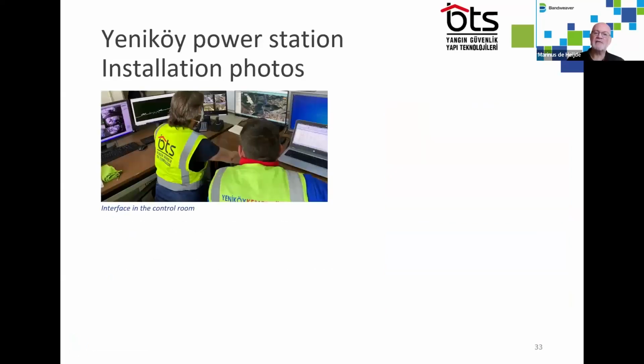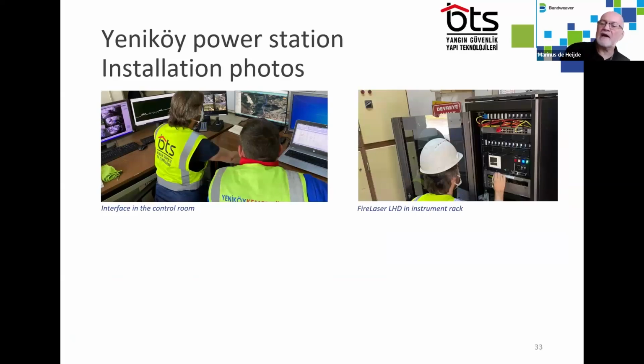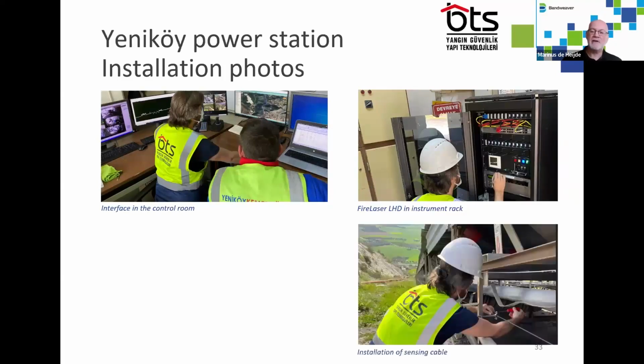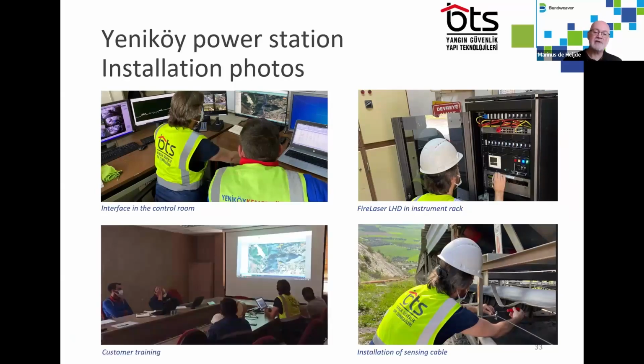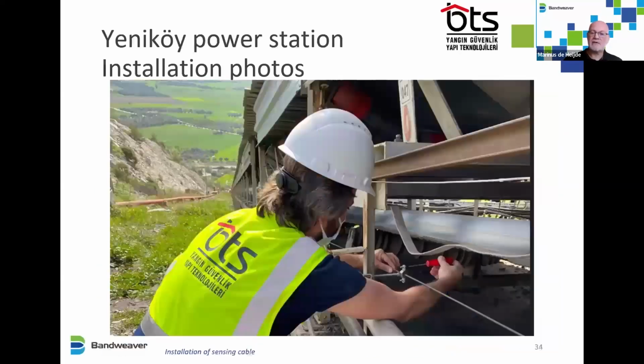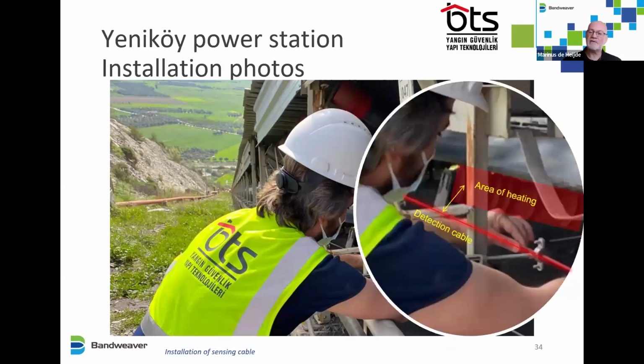So here is where you can see the interface in the control room and the FireLaser in the instrument rack, and you can see the LCD screen there. The installation of the cable itself, and as you can see, it was installed quite close to the bearings themselves. And as you can see, OTS is our exclusive distributor for Turkey. They also provided customer training locally. So here's where you can see a little bit more detail on the installation of the cable itself. So you can see it is quite close to the bearing itself, or the area of heating and the detection cable.